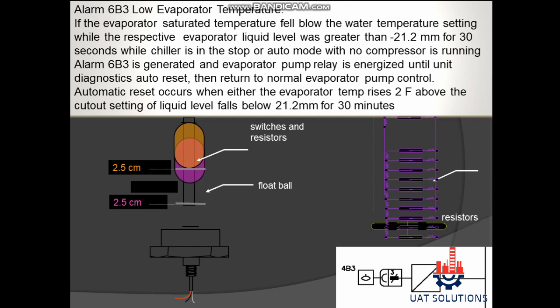Automatic reset occurs when either the evaporator temperature rises 2°F above the cutout setting, or the liquid level falls below minus 21.2 millimeters for 30 minutes.